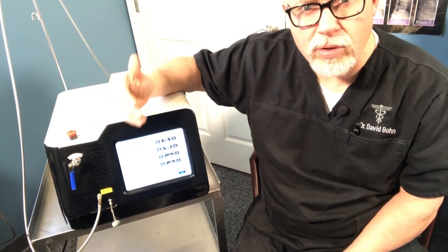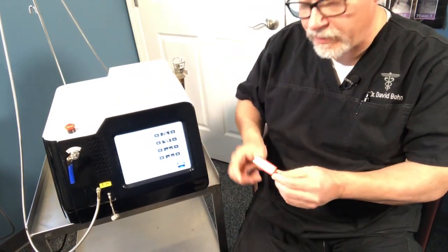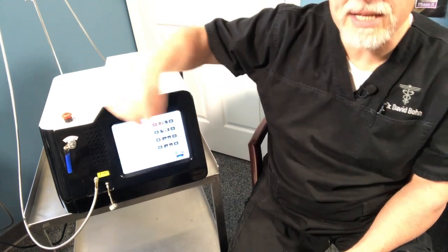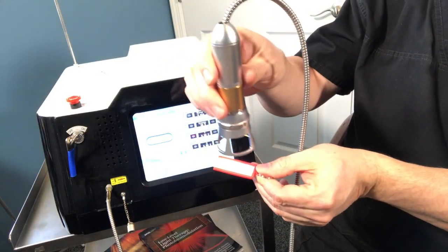The next time you push A, that same protocol will open up. When you're ready to start, as soon as you touch the standby button, your laser is going to be hot. If I shine the laser onto the test strip, I get a green reflection — that tells me I am producing a laser. The laser is functioning. That's your test strip and that's what it's for. It doesn't show up great on camera, but you can see the yellow or green strip there.